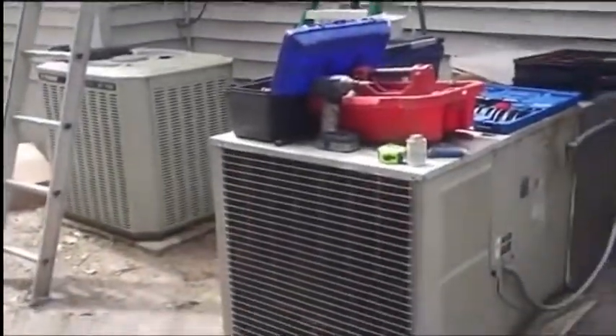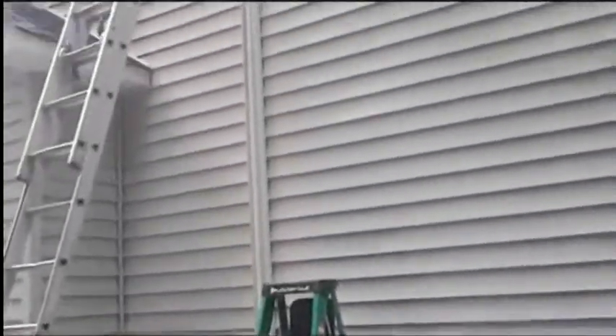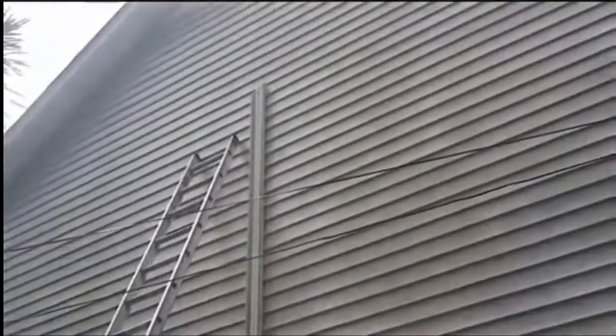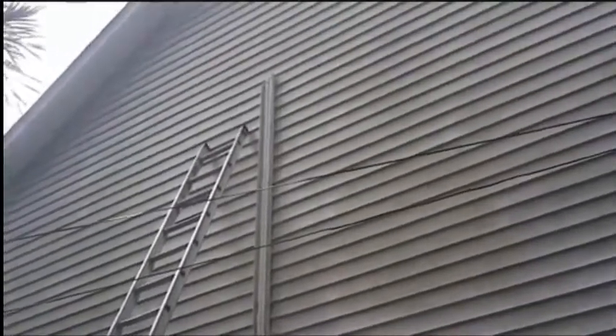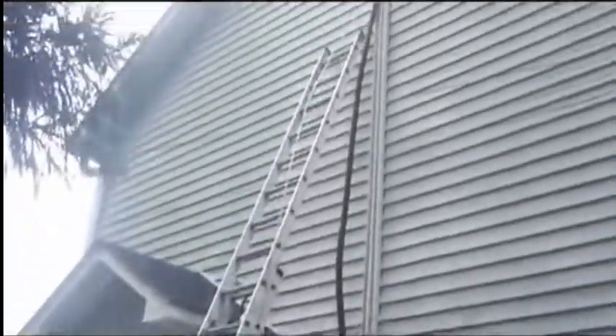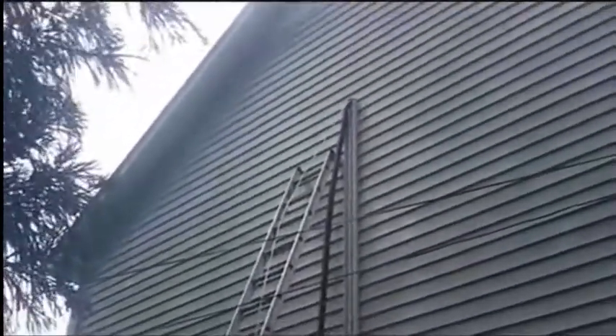I'm going to get everything in that channel, and then tomorrow morning Ari Michael's going to deliver our 15 SEER heat pump and air handler. Alright, now I'm feeding the line set up. It's a little bit more difficult, especially single-handedly. The 3/8 line's not too bad, liquid line's not too bad, it goes up pretty easy. I'm going to go up in the attic and make sure we got enough.